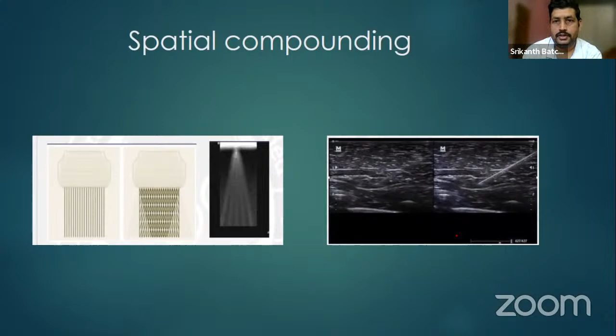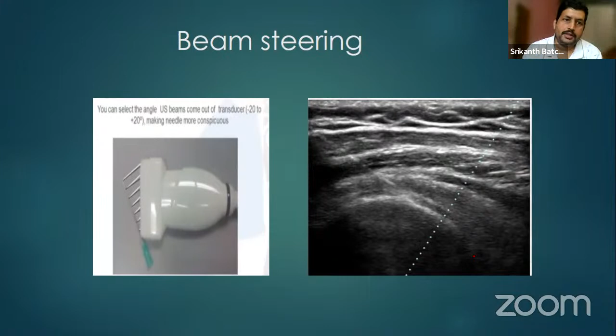Next is beam steering. This is similar to what we do manually with the heel-toe maneuver. In heel-toe, if the needle is not visible, we turn the ultrasound probe towards the needle. So in this, the machine does that. If you remember a 1990s movie, a comedian will be selling brushes. You don't need to move your brush, you just need to move your head, and the brushing will be done. It's the same thing. If you are not able to do the heel-toe maneuver correctly, in modern machines there is beam steering, where it will identify the hyperechoic shadow, and when we turn it on, it will steer in that direction so that the needle visibility will be more. Instead of the routine perpendicular direction the beams go, when beam steering is on, it will turn towards the needle.